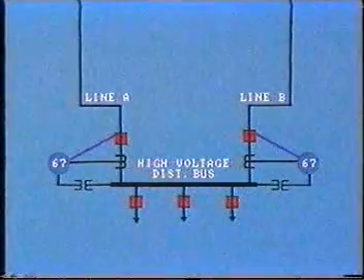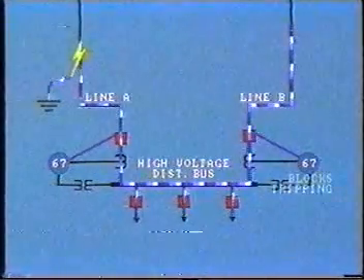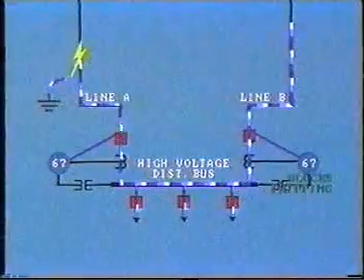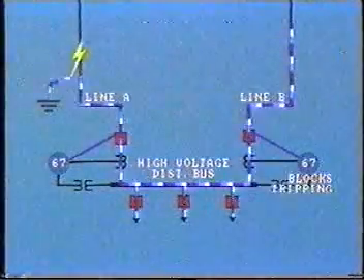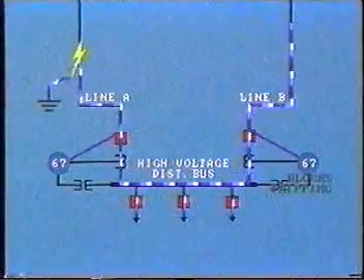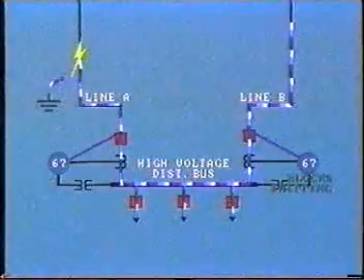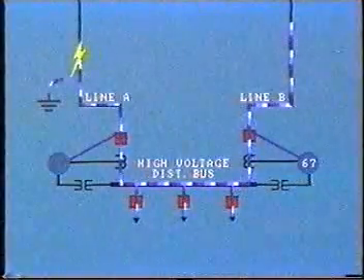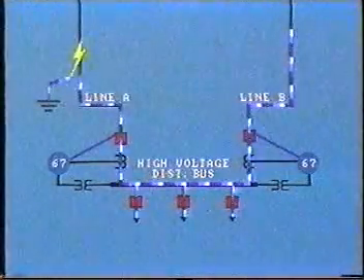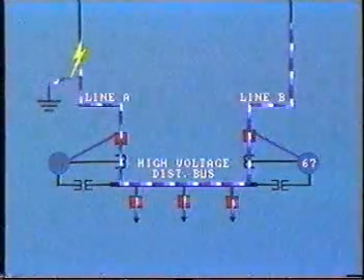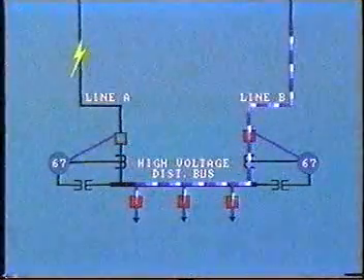With a line A fault, the directional element blocks the overcurrent relay on line B from tripping when current flow is into the bus. But it will allow operation of overcurrent relay A to trip when current flow is out of the bus.